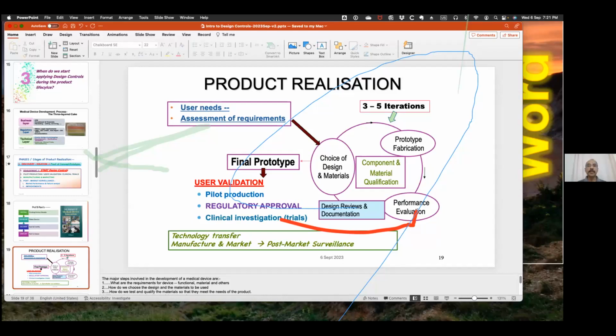Then the next question is, what are the charges for certification and compliance for medical devices in India? I have no idea right now because I have not gone through that process. It varies depending on the risk class. As I said, Class A devices need just a simple registration. There are some licensing fees. Right now in India, I think the fees are relatively modest.